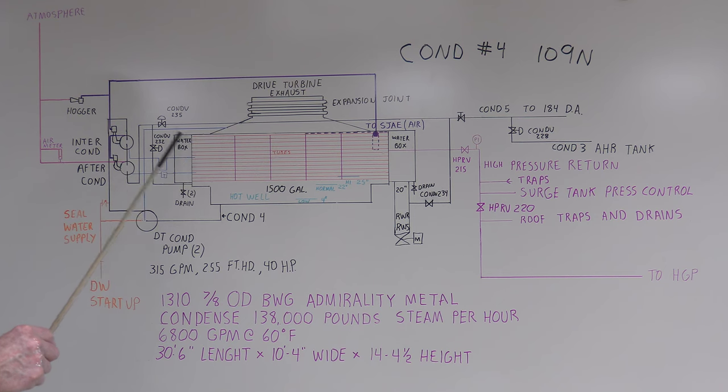The vent line was critical in order for this pump to start. It was a two-stage pump - the center impeller was a double suction, and then that fed the two second stage impellers on each end of the pump that created pressure on the shaft so it couldn't leak air in. For startup, use demin water through a check valve that would feed the pump seals. When the pump is running, you take off the discharge through a check valve.